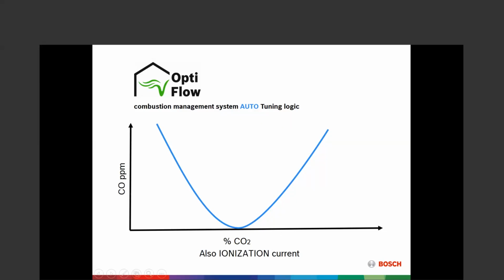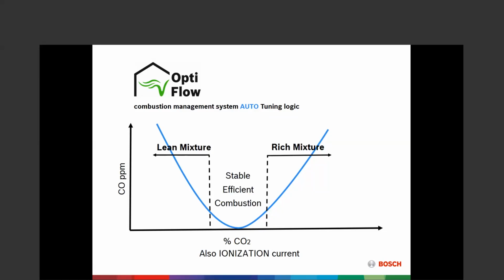So we use this ionization current to allow the unit to set itself up for the installation where it is, as far as the gas and air quality and all that kind of stuff that's coming into that unit. Vent length, and all of those things are taken into account. It sets itself up for that with the ionization current. So it actually monitors what that current is through the flame sensors. Over here we have our lean mixture, over here we have a rich mixture, and where do we want to sit? Right here in the middle, with that stable, efficient combustion. And this OptiFlow makes sure on startup that we set that up that way.